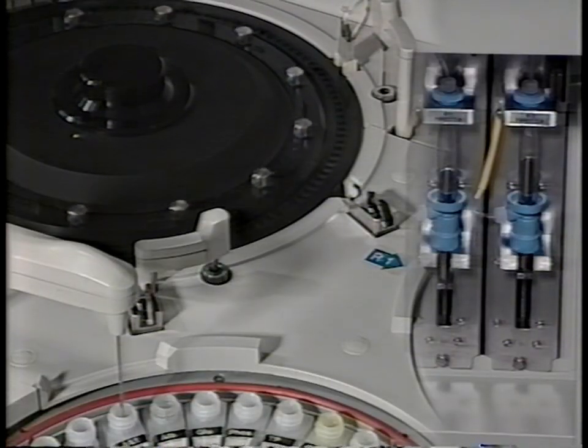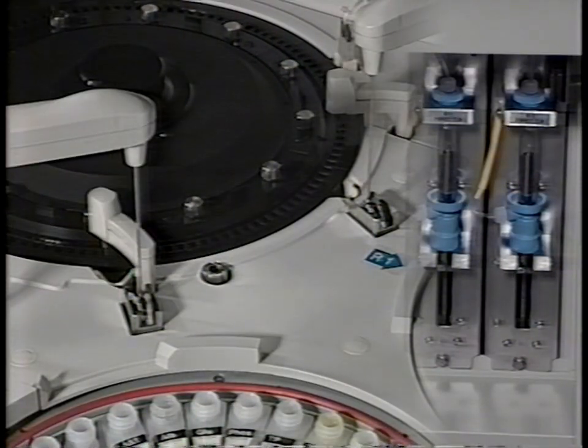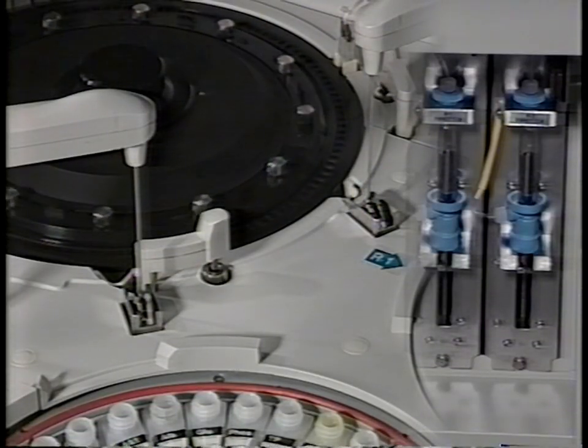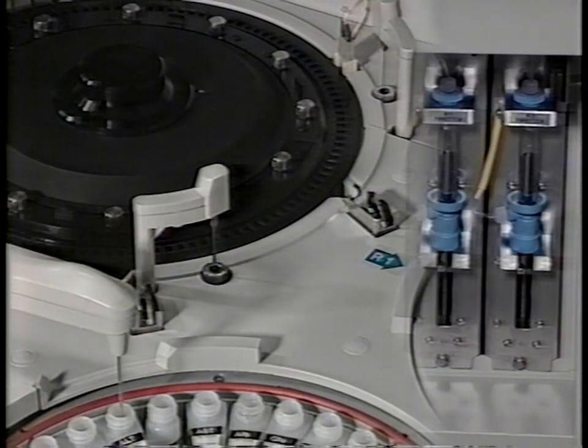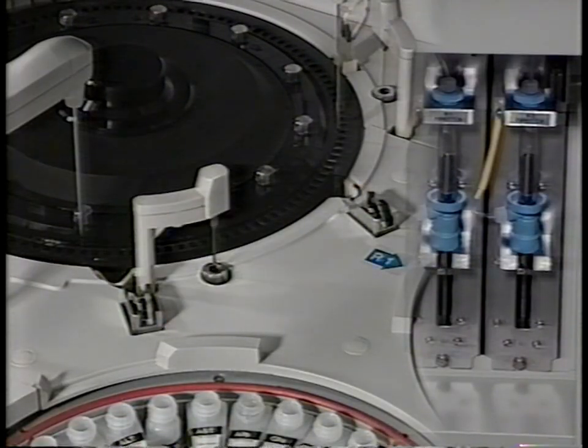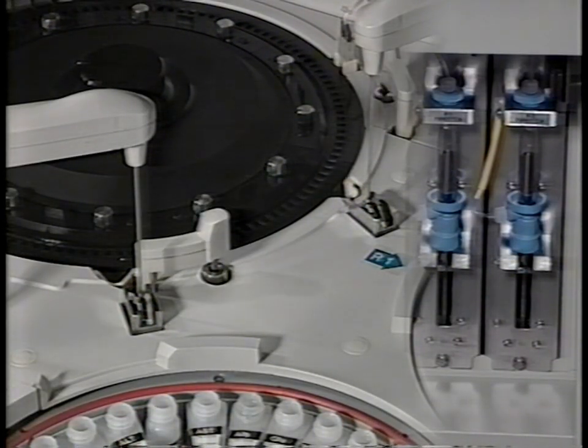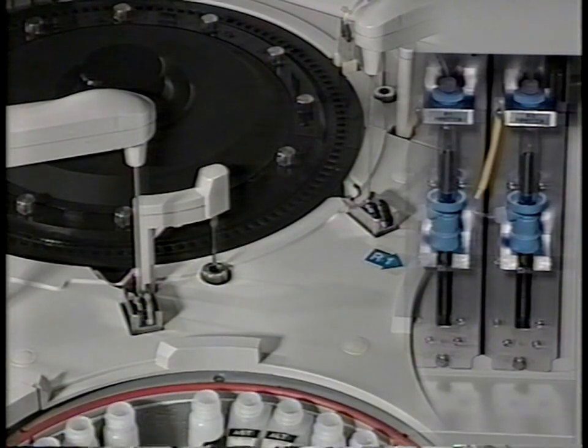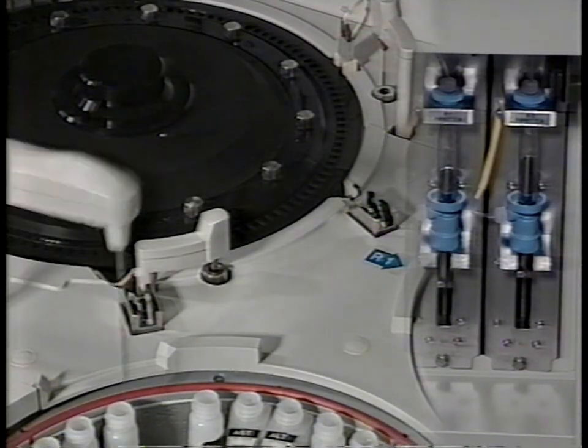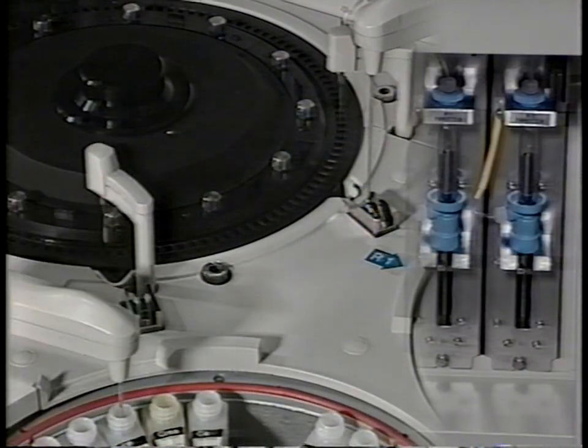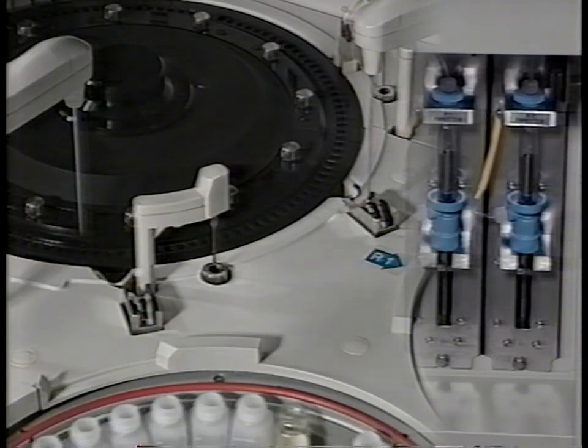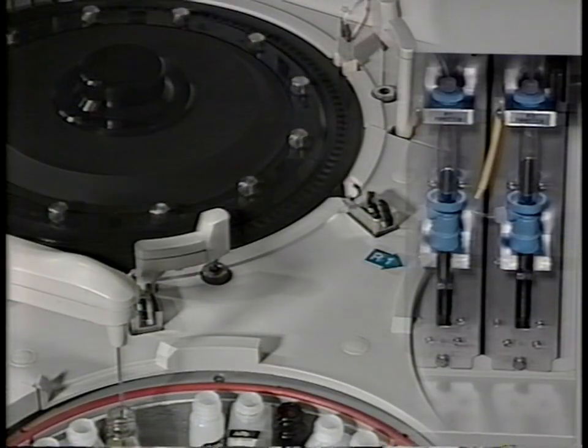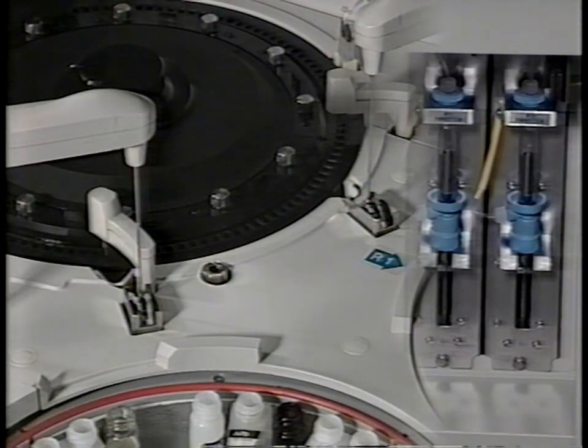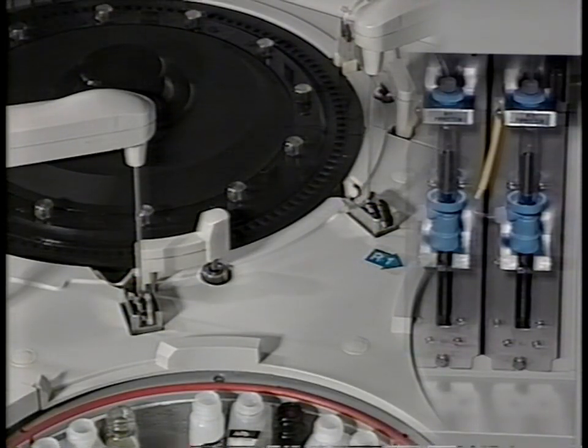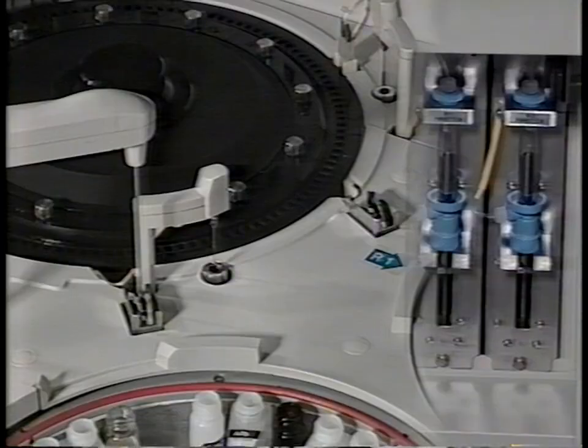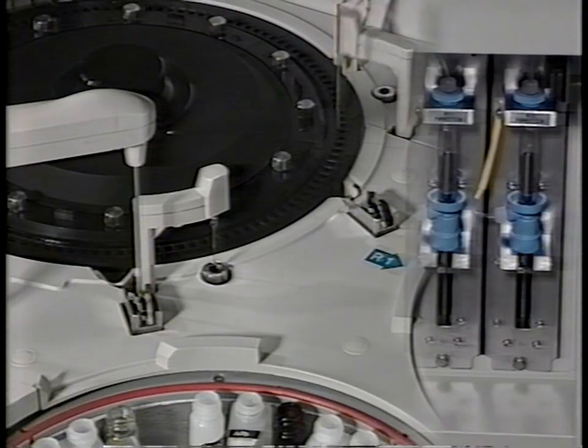The positive displacement reagent pipetters, shown here on the right side of the screen, are connected with plastic tubing to the reagent probes. Reagent aspiration and dispensing occurs in 3 stages. The appropriate reagent disc rotates, bringing the required reagent container into position at the reagent aspiration station. The appropriate reagent probe is lowered into the reagent container, and the reagent pipetters aspirate reagent into the reagent probes. The probes then dispense it into the reaction cells. When the reagent dispensing is complete, the probes return to their home position where they're rinsed with deionized water.